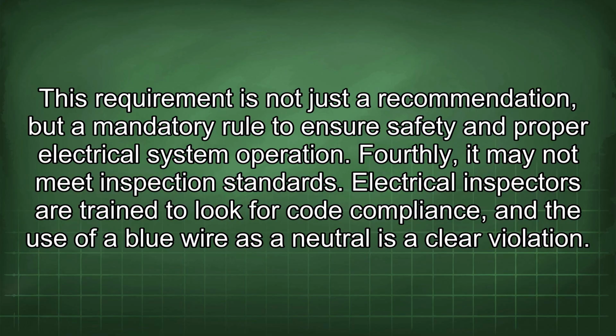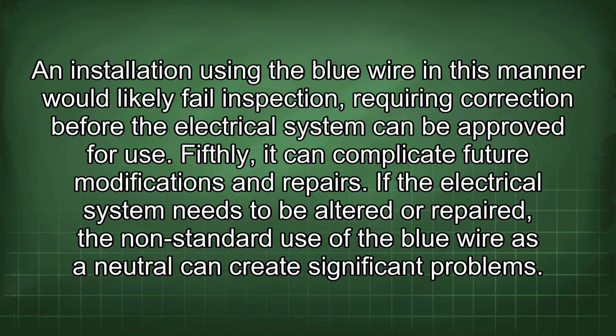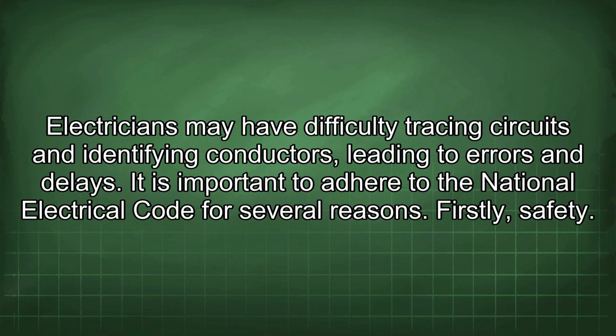Fourthly, it may not meet inspection standards. Electrical inspectors are trained to look for code compliance, and the use of a blue wire as a neutral is a clear violation. An installation using the blue wire in this manner would likely fail inspection, requiring correction before the electrical system can be approved for use. Fifthly, it can complicate future modifications and repairs. If the electrical system needs to be altered or repaired, the non-standard use of the blue wire as a neutral can create significant problems. Electricians may have difficulty tracing circuits and identifying conductors, leading to errors and delays.